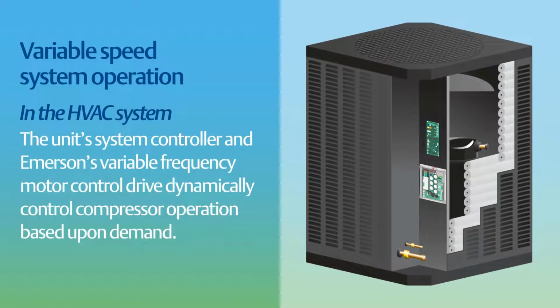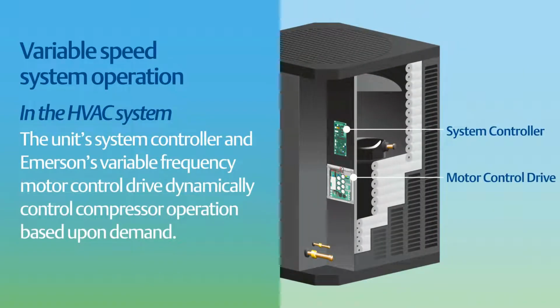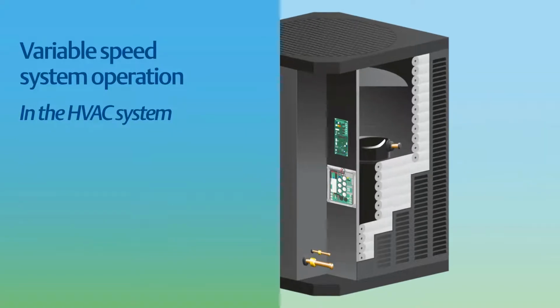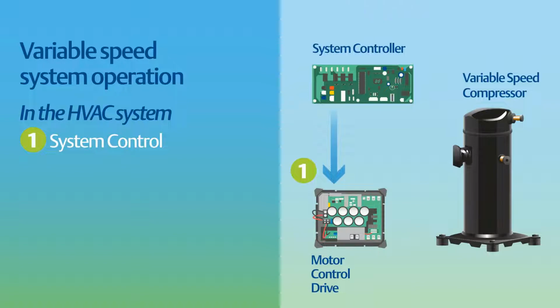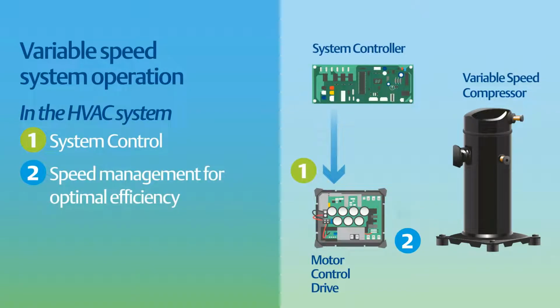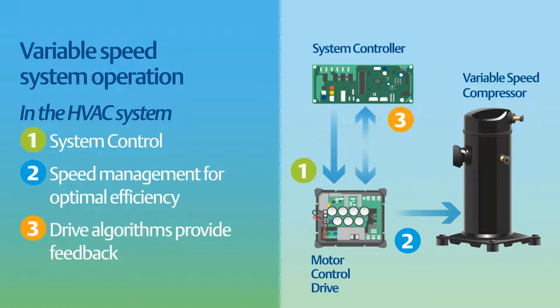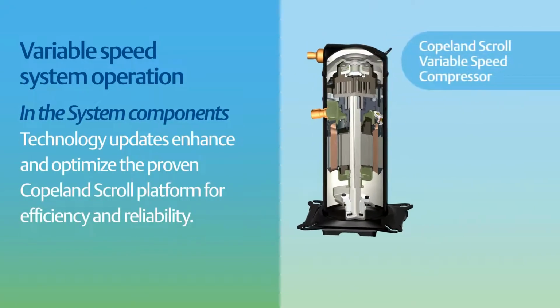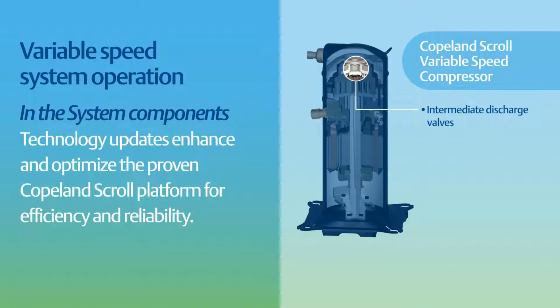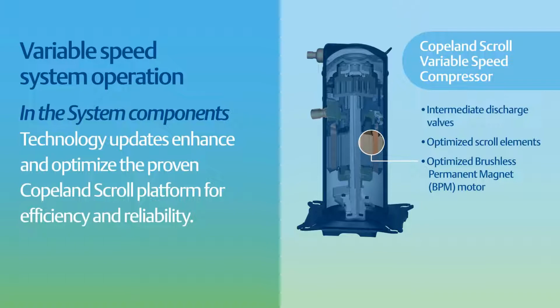Within air conditioners and heat pumps, the unit's system controller and variable frequency motor control drive dynamically controls compressor operation based upon demand. First, the system controller sends speed signals to the variable frequency motor control drive. Then the drive dynamically adjusts the brushless permanent magnet motor operation. The compressor speed is managed to ensure optimal efficiency and protection from any adverse conditions. And finally, the drive algorithms provide feedback to the system controller to optimize operation. At the component level, technology updates enhance and optimize the proven Copeland Scroll platform for added efficiency and reliability. These features include intermediate discharge valves to boost efficiency across a range of conditions, optimized scroll elements for improved performance, brushless permanent magnet motor technology for maximum efficiency, and a positive displacement oil pump to ensure reliability.